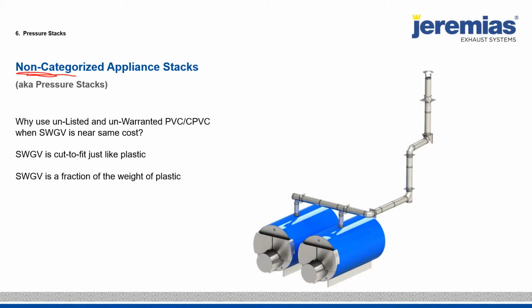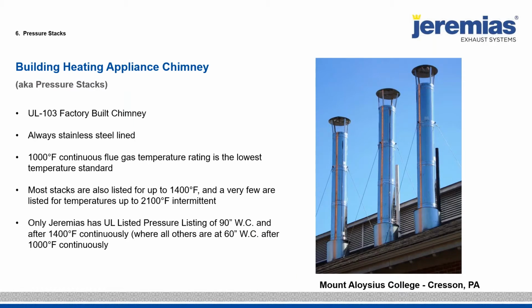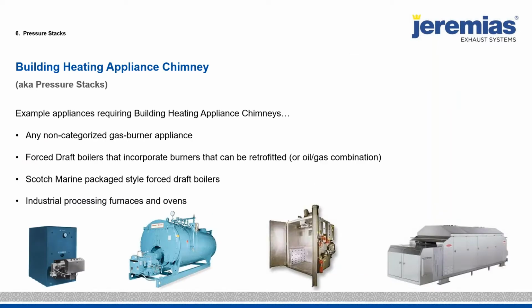Okay, if the appliance is not categorized, we call it non-categorized appliance stacks, or otherwise, a lot of people know them as PS pressure stacks. So that's a UL 103 standard, which is a 1,000 degree temperature listing. Some go up to 1,400 degrees, and all of them are listed at 60 after 1,000 degrees, where Jeremias is listed at 90 after 1,400 degrees. The reason we did that is because we want to make sure that you could easily add Jeremias to your specs, the name, because we exceed every part of your specification.